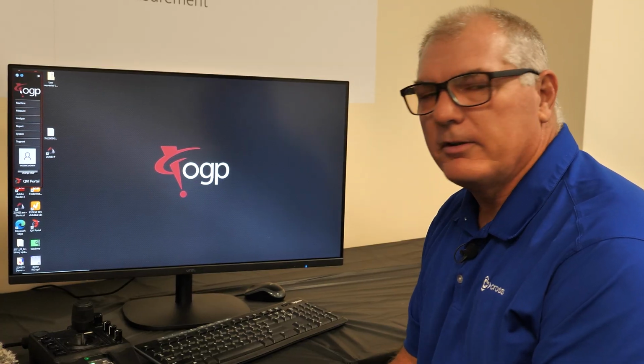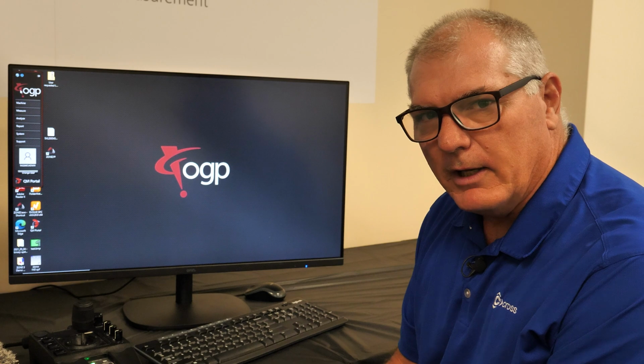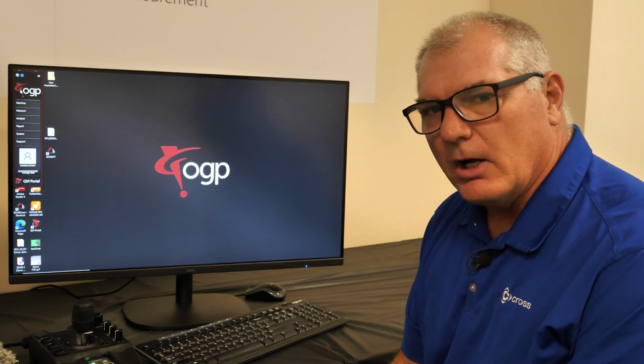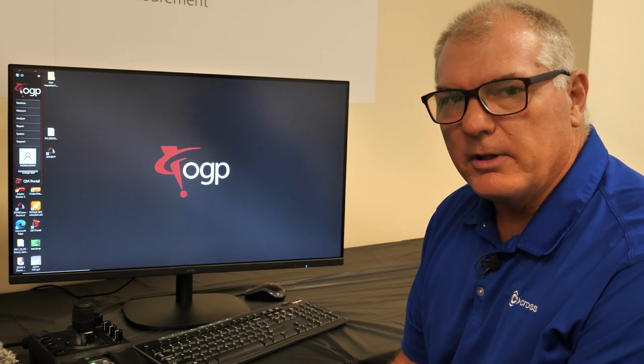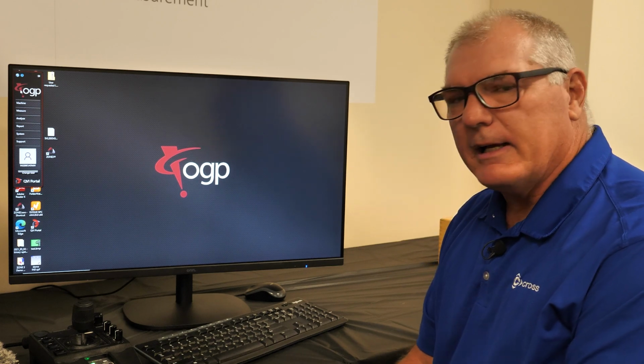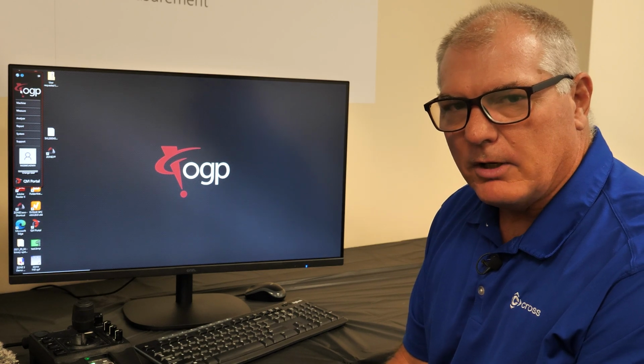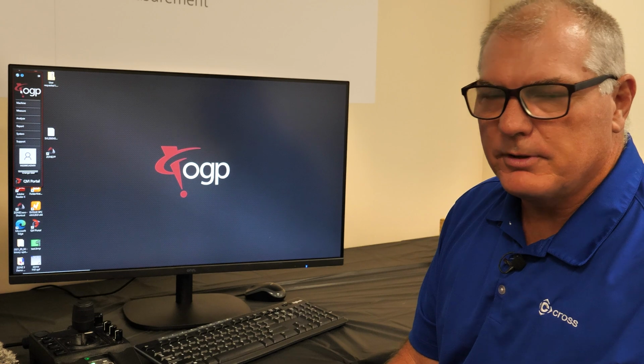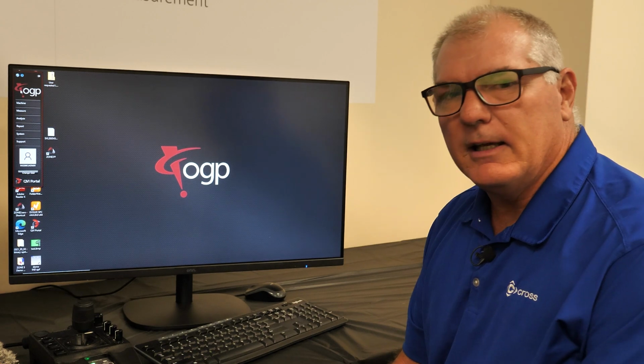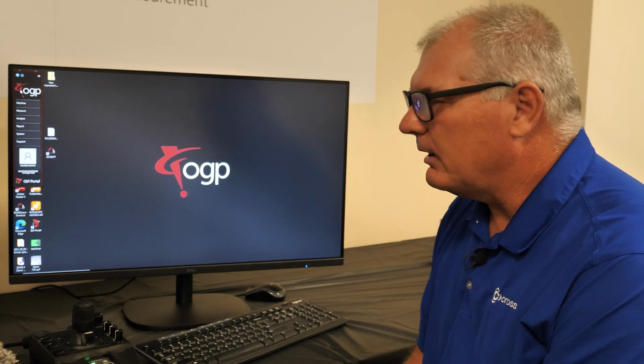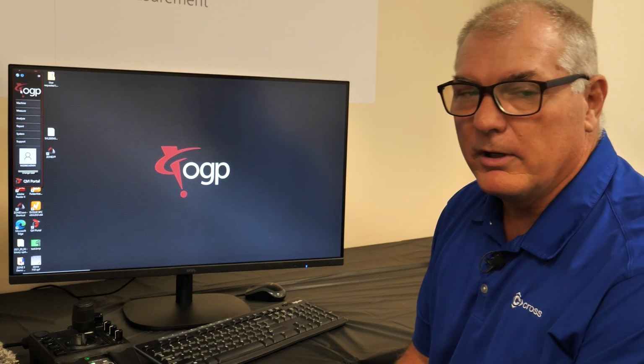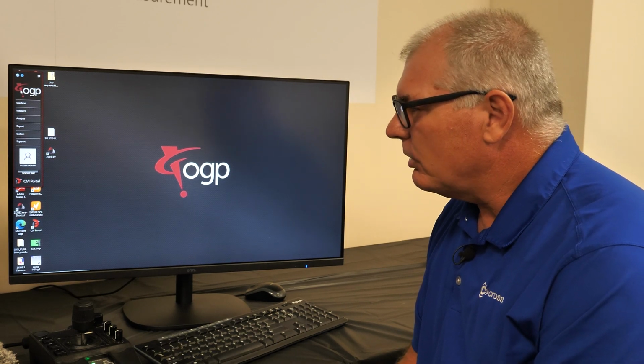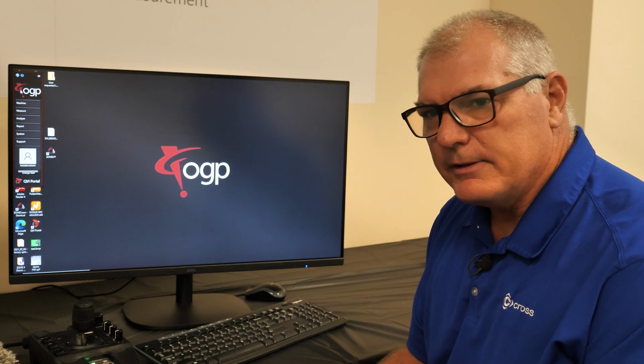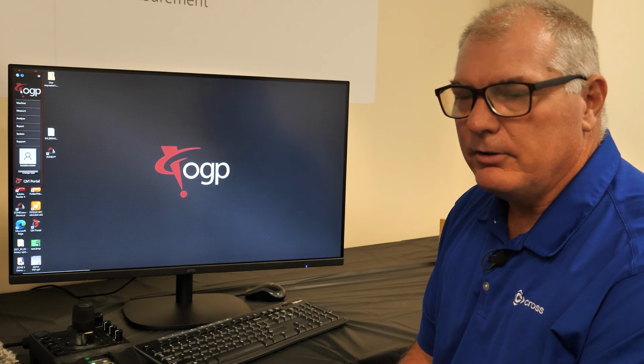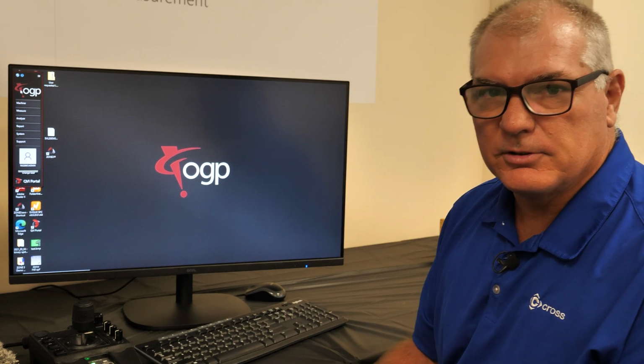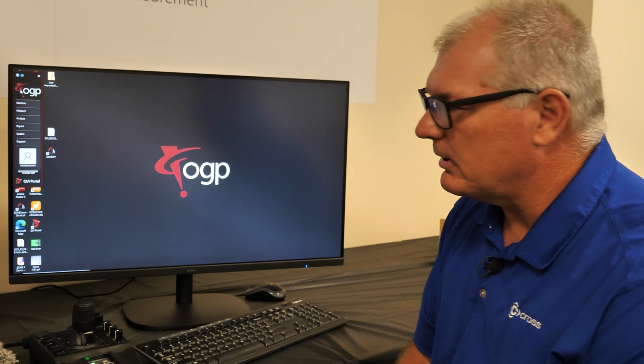All right, welcome to our tip section on how to use the QVI portal. The portal is software that is shipped with each OGP machine, which allows us to access the operating software such as Measure X and Zone 3, as well as SPC and calibration activities such as touch probes or even the stage calibration. So we want to use different access rights inside of Portal to allow users to gain access to just their software, maybe not their calibration software.